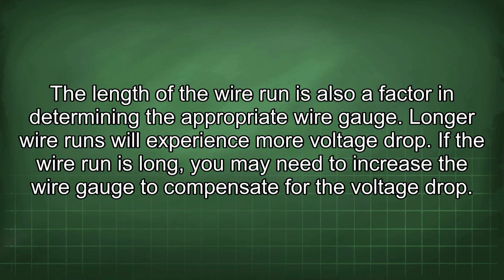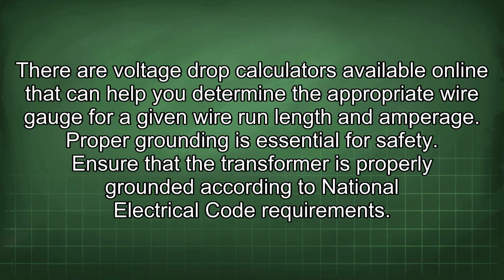The length of the wire run is also a factor in determining the appropriate wire gauge. Longer wire runs will experience more voltage drop. If the wire run is long, you may need to increase the wire gauge to compensate for the voltage drop. There are voltage drop calculators available online that can help you determine the appropriate wire gauge for a given wire run length and amperage. Proper grounding is essential for safety.